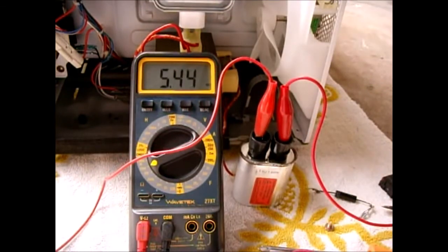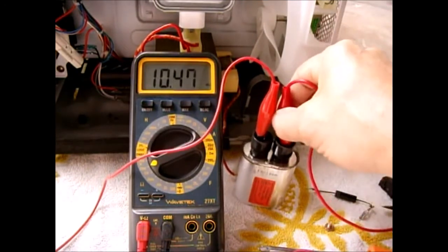It needs to start from a low reading and go higher, resistance-wise. As long as it does that, it's good. You don't want a low reading. If it's high and the resistance stays where you connected it or moves lower, that's a problem. It needs to change from low resistance to high resistance, in the mega-ohms, for it to be a good capacitor.